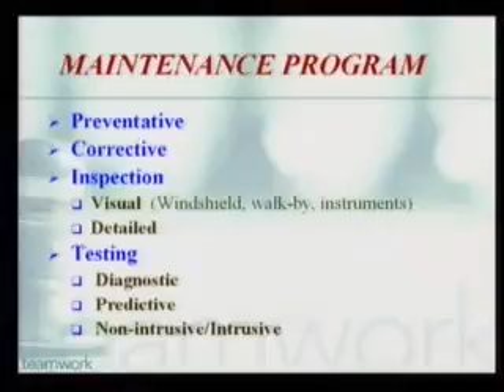And general guidelines that we use is we follow industry standards for substations as well as our transmission and distribution equipment. We follow the manufacturer's recommendations as to how often we should do any of the inspection or testing that we should do, or as needed. The as needed portion really applies to a lot of the equipment that we have because they have age, they have a lot of mileage, so to speak, a lot of operations on them. So we may do a lot more inspection or repairs on this equipment.